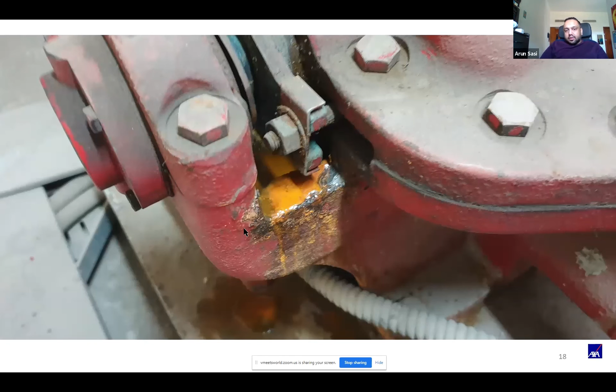This is again a site where the fire pump had been serviced. You could clearly see there is corrosion in the gland packing. In many of the cases, I see flooding from the gland packing. So these mean that your fire pump is not going to function in accordance with the design. So as a client, you might be thinking, I've already paid for the contractor to come in and visit the site and maintain my equipment. But then, in the event of a fire, if the pump doesn't function, all of this kind of becomes a moot point.